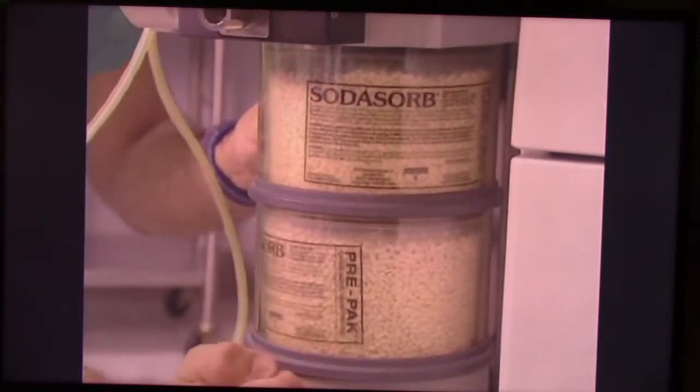In Grand Rounds this year, we had a discussion on pouring water into the absorber, and at our institution, they said not to do that. If you had any concern about it, pretty much take off, if not both, then the lower canister. And replace it with fresh. Does the insert on the absorber say that you can pour water into it? I don't know, but I know you can. And I know that there's been at least one study that suggests that you will rehydrate the absorbent simply by pouring water into it.